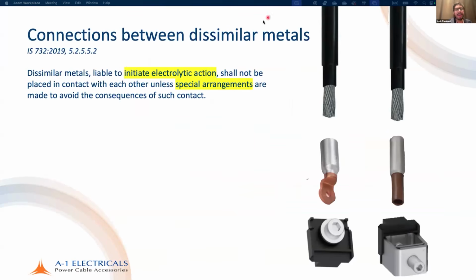Hmm. So, I mean, there has to be a product standard, and that has to be either tested or verified according to it. So, you just take a strip. I'm not aware of any IEC product standard for this. No, there is none. The strips are there, but a proper strip should be used, according to the standard itself. If you have a normal aluminum lug and it is to be attached to the copper bus bar, there are washers, but a washer with proper weight and proper thickness should be used. It is not that you can just put anything.